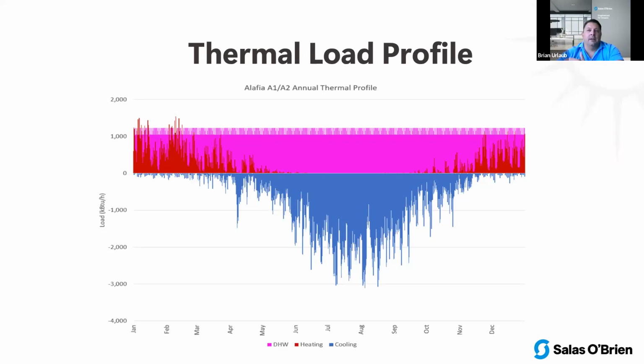Okay. We actually did a little analysis where we just took the cooling out of the equation and the sewage heat recovery system did 100% of the heating. The problem is that's not reality. Reality is we have a tremendous amount of cooling. And when you add that in to the system and look at your long-term effects of the ground loop, we have to be very careful in how you size that. So we can maintain a healthy system over time.